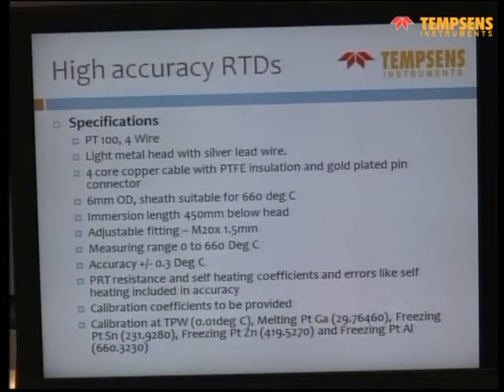Then we are doing some special RTDs which are used for turbine efficiency testing. You have the inlet of the turbine and outlet of the turbine, and how much power is produced. In case BHEL is doing a turbine for a customer, they promise that the efficiency would be 95%. They prove this by using such thermal sensors, in which they have the inlet temperature, outlet temperature, and how much power is produced.